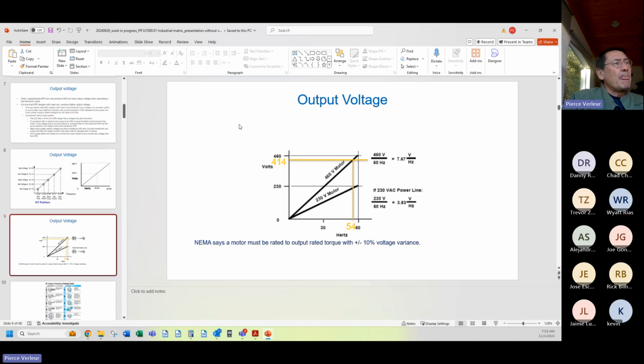Output voltage. This is a typical output voltage curve of a VFD, 230 and 460. Let's just talk about the 460 volt application. At 30 hertz, we're at half voltage. At 60 hertz, we're at full voltage. That's what the motor likes to see.